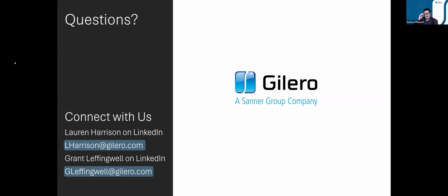When considering whether or not to offer the clearance or the approval, FDA is going to pay most attention to your validation data. But you are going to have to provide your UE file as part of your DHF, and in the HFE UE summary report that summarizes all of your usability engineering activities that occurred. You're going to summarize all of your evaluations. As a matter of fact, I believe that one of the headings in the template that the FDA gives specifically references your earlier evaluations, because they want you to tell the story of how you conducted an evaluation, made the product better, and so on.